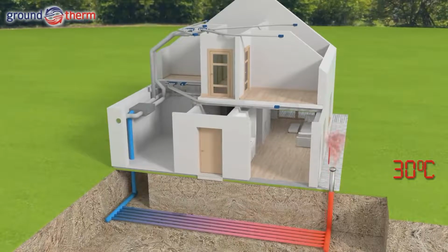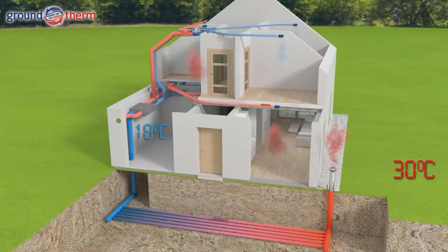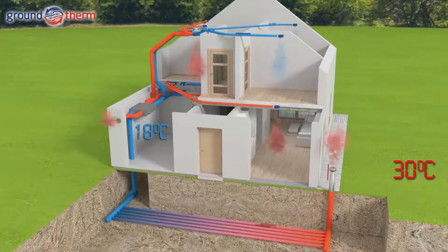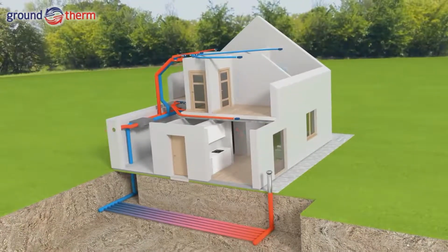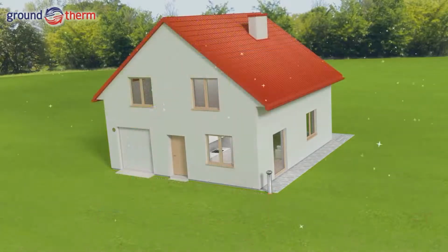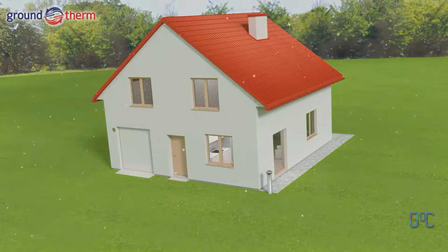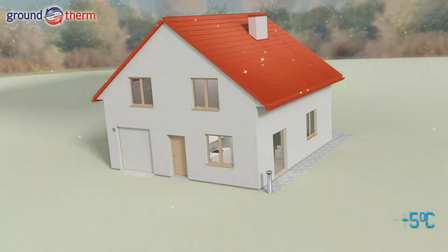In summer, the hot air passes through the ground heat exchanger and is cooled from 30-something degrees Celsius to approximately 18, and when distributed inside the building, it creates pleasant, comfortable and healthy climate in it, even on the hottest of days. The suitable filters catch insects and dust from the supplied air. The air supplied in this way is free of excessive humidity, which significantly increases comfort even on the hottest days. At the same time, the air is not over-dried, as is the case when the standard air conditioners are used. Moreover, the cool obtained this way is practically free. It is supplied by Mother Earth.